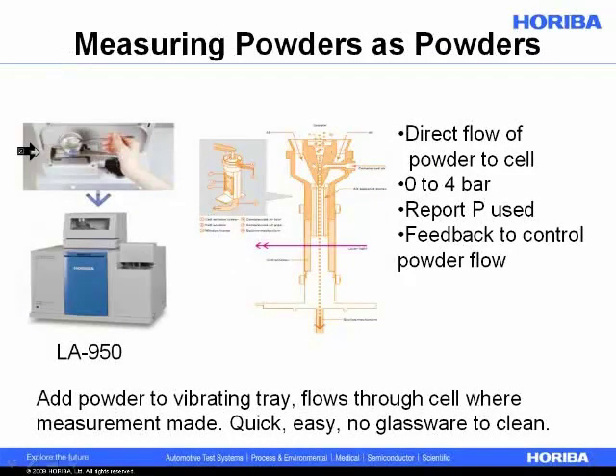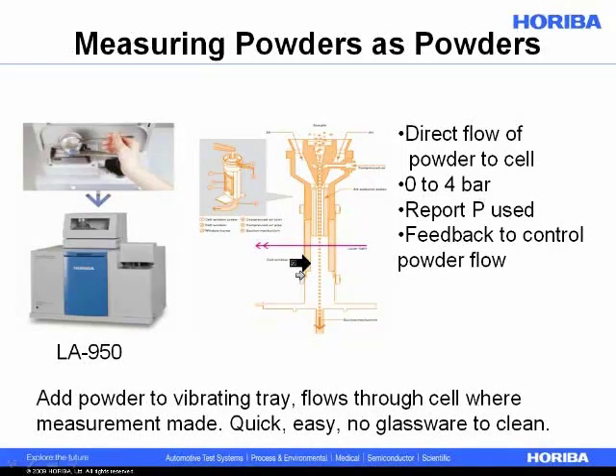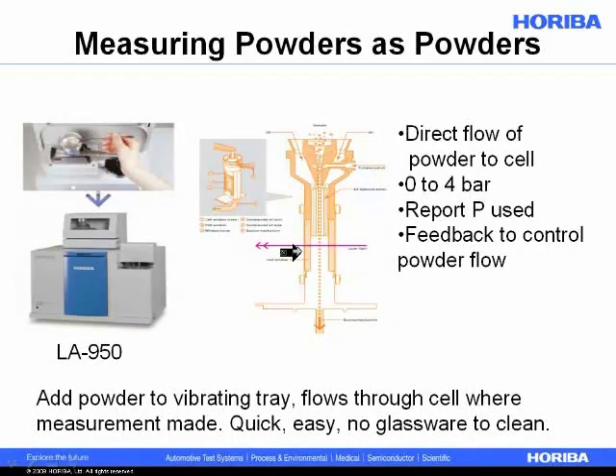When we want to measure powders, we can measure them directly as powders using the LA-950. You see here adding the powder to a vibrating tray; in the middle is a picture of the venturi, and this is the dry powder cell used to present the powder to the instrument for measurement. Compressed air is entered here — anywhere from 0 to 4 bars. We draw the powder and drive it through the measurement zone and collect it in a vacuum, with a feedback control loop to maintain constant mass flow through the optics for the most reproducible measurements.